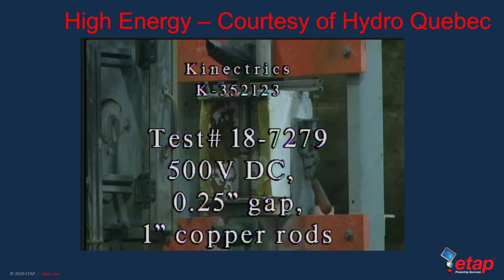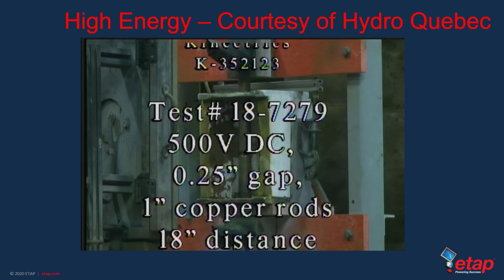For this next video, which is the last video in this family of high energy videos that I have prepared for you today, we'll have an available DC short circuit current of 20,000 amps and a duration of 2 seconds. This is actually more than twice the arc duration of the previous DC arc fault event from the video that we saw a second ago. The total incident energy that was recorded from this test actually exceeded 40 calories per centimeter square.